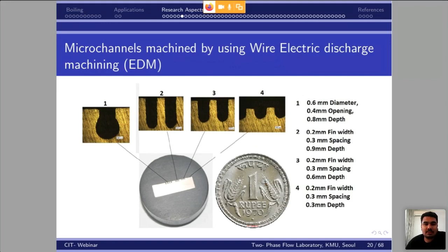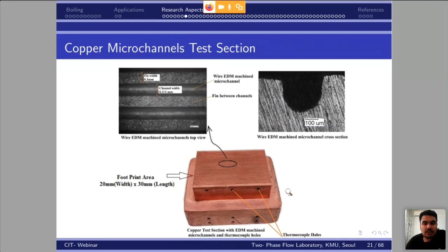This is the heat sink. You can see it is made of copper, and you can see how the channel is machined. We are mainly concentrating our talk on these small size channels, not on big size channels, because the big size channel has already been explored much. So it is better to look at what is happening inside small channels during this flow boiling. These are the channels with 0.3 mm diameter, that is nearly 300 microns. This is the heat sink with 31 parallel channels you can see here. This is the testing block actually. We can heat the block and allow the fluid to pass through and test the performance.